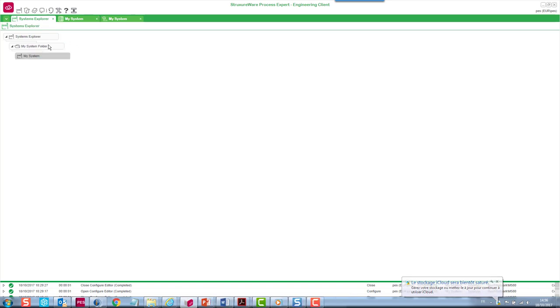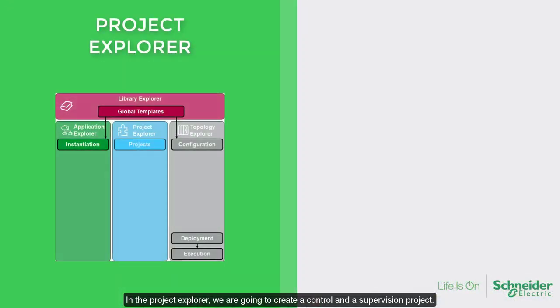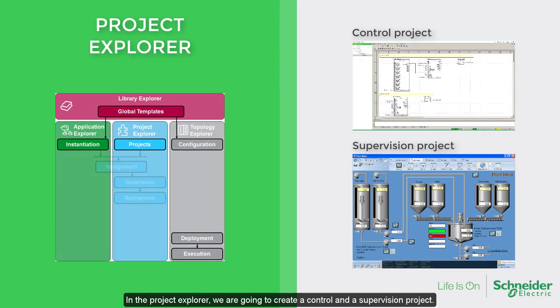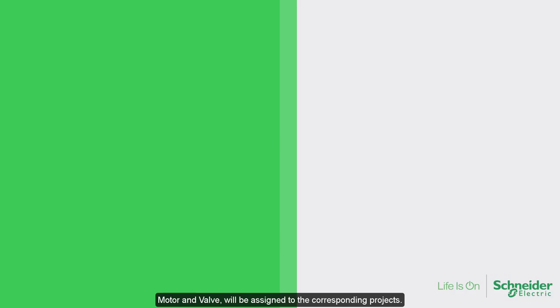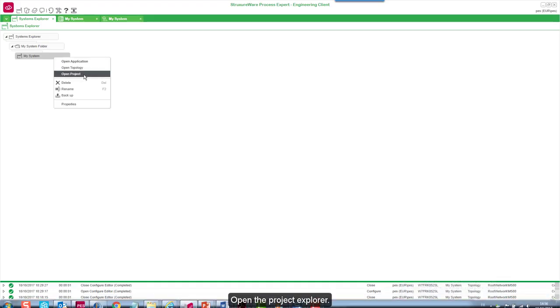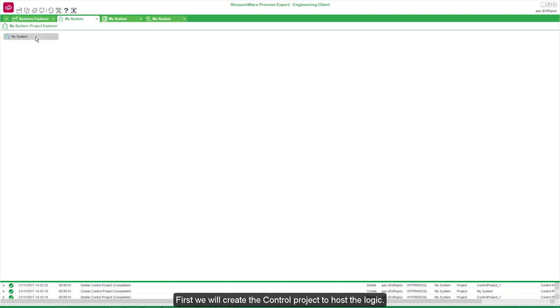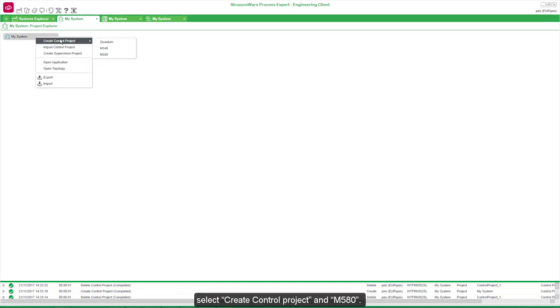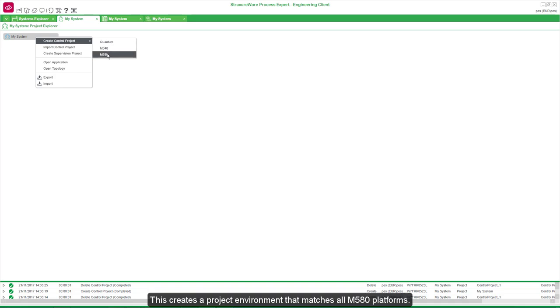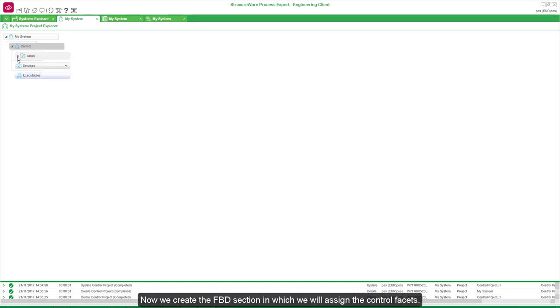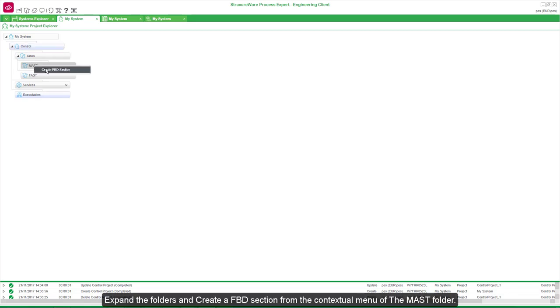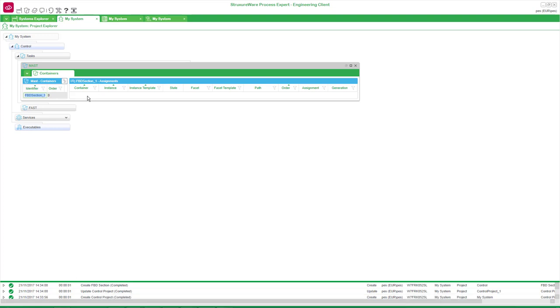We can go back to the system view. In the Project Explorer, we are going to create a control and a supervision project. The logic and the supervision facets embedded in the object instances — motor and valve — will be assigned to the corresponding projects. Open the Project Explorer. First we will create the control project to host the logic. Open the context menu, select Create Control Project, and choose M580. This creates a project environment that matches all M580 platforms. We name it Control. Now we create the FBD section in which we will assign the control facets. Expand the folders and create a FBD section from the context menu of the MAST folder. Name it Discharge.